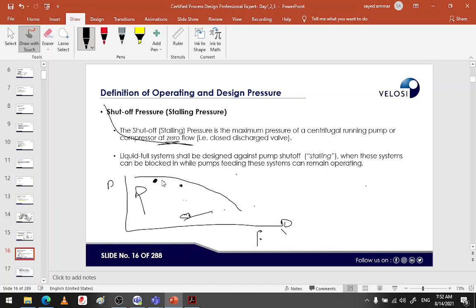Most vendors or manufacturers try to keep this from 5 to 10%, to make sure that the compressor will not do a lot of work or consume a lot of electricity or fuel. What we are trying to say here is that when you define your maximum or worst-case scenario for the design pressure, consider the shut-off pressure, this point, and do not rely on the operating point for the compressor or even the pump.